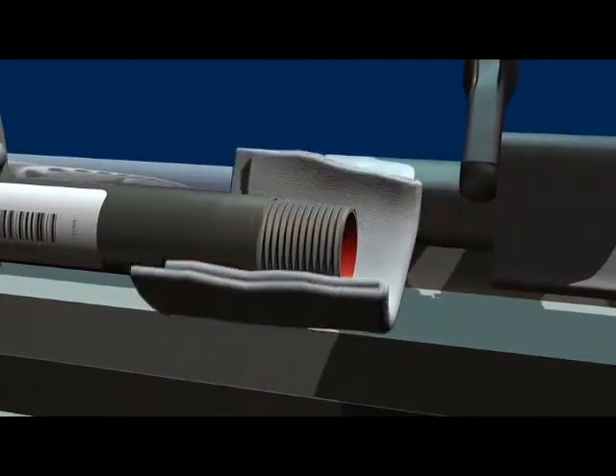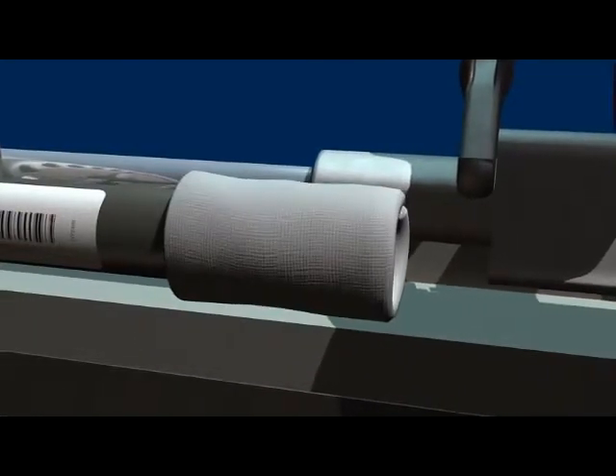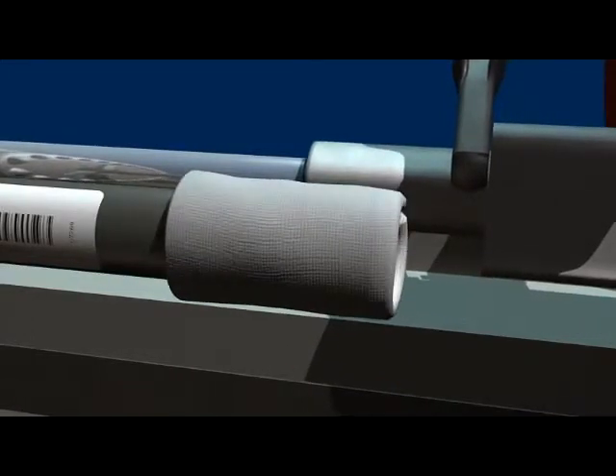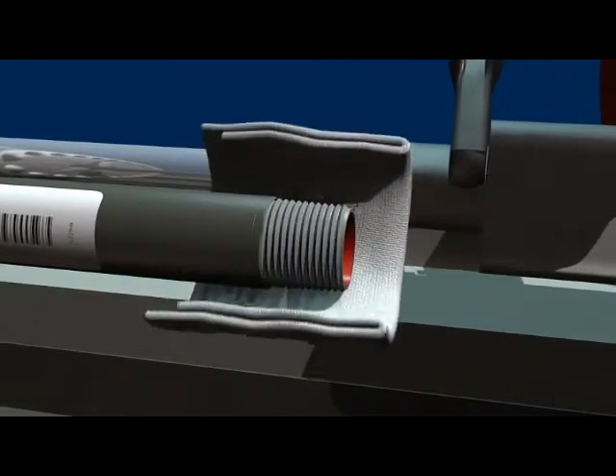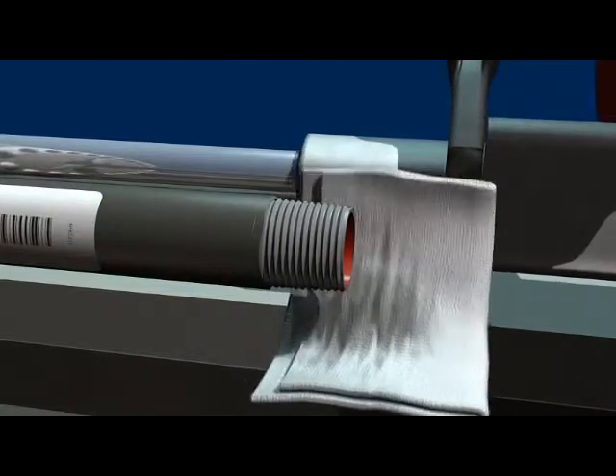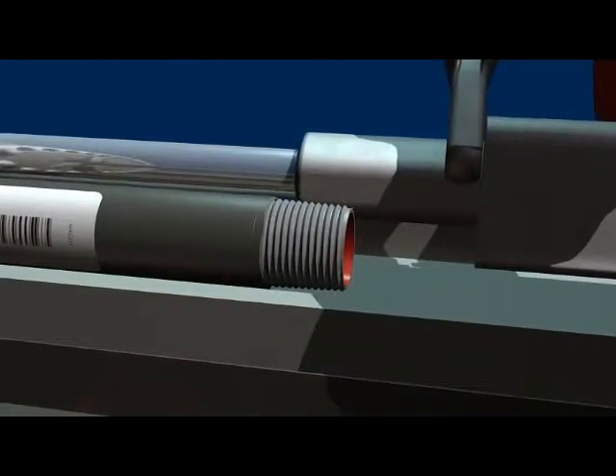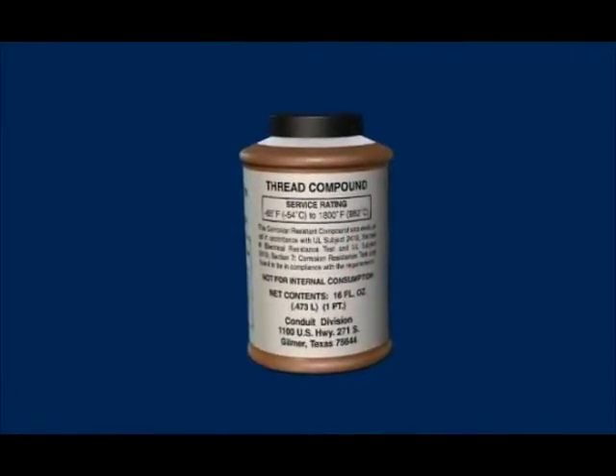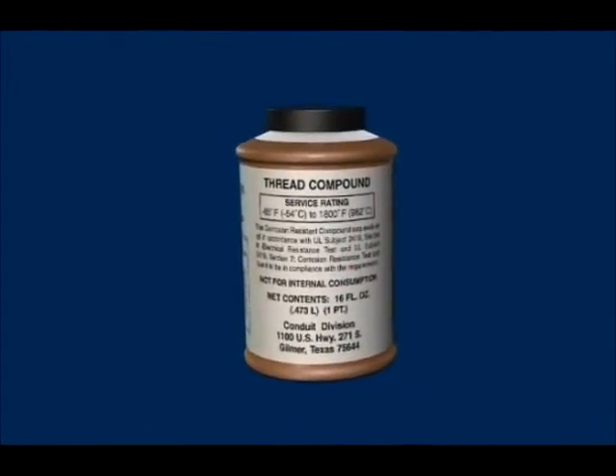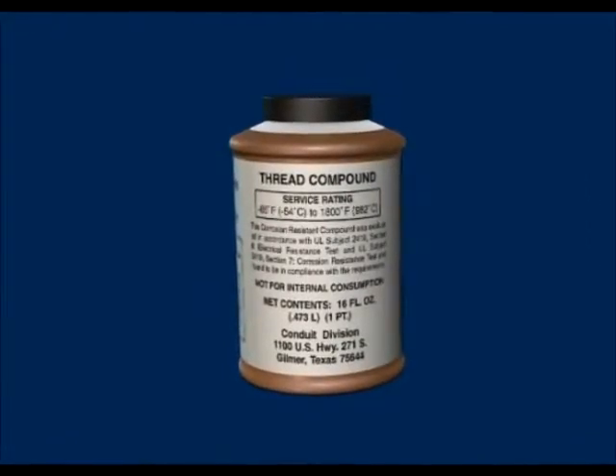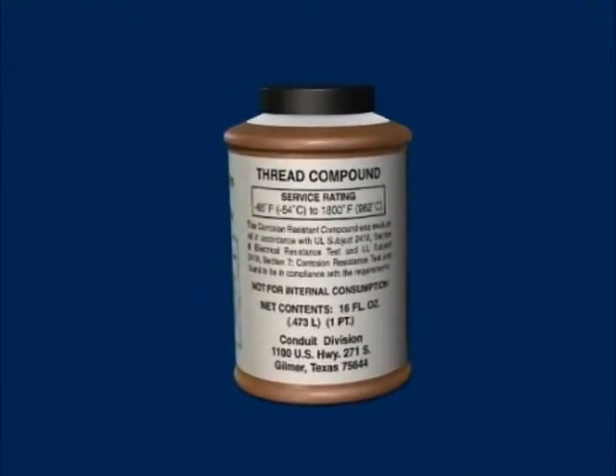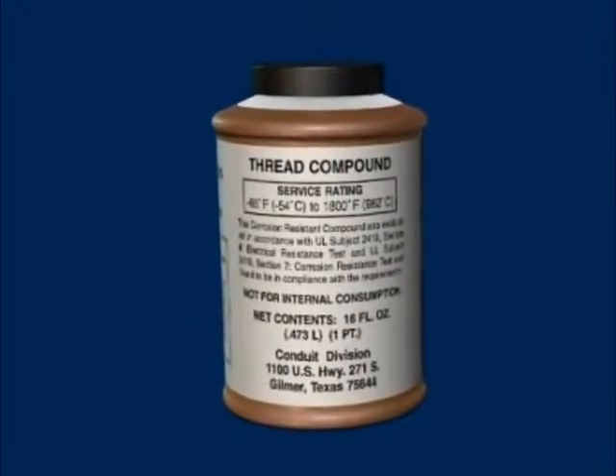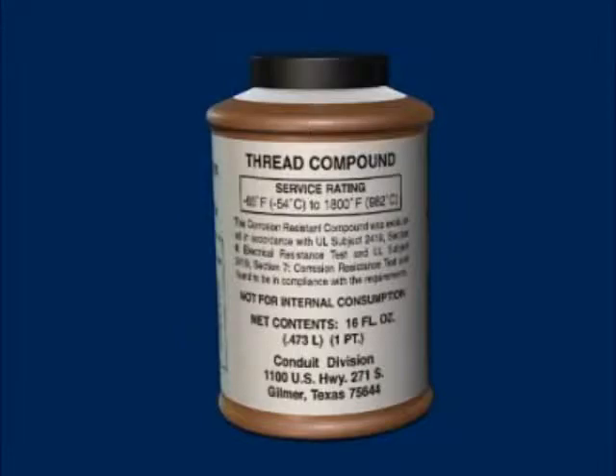Degreasing is important to ensure that the thread compound will adhere to the unprotected steel. Bare steel resulting from field cut threads is the most vulnerable area to corrosion in any conduit system. Therefore, thread compound must be used on all field cut threads and internal reams. Proper use of thread compound will ensure a reliably sealed installation. Thread compound has been developed as a protection for bare metal and is available in pint cans.